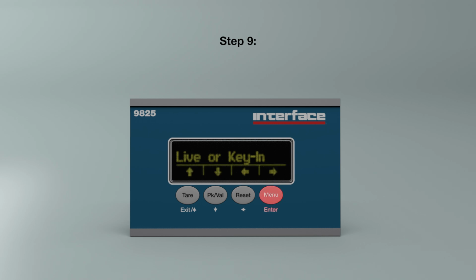Press the menu key to scroll right until the menu item called Set Positive Span is displayed. Press the peak and valley key to begin setting the positive span. Fixture will be displayed. For this example, we will be using a load simulator to provide millivolt per volt input values. Make sure the load simulator is set to output 0 millivolt per volt, then press the menu key to set the fixture value. A dashed line will migrate across the display as the 9825 records the input.